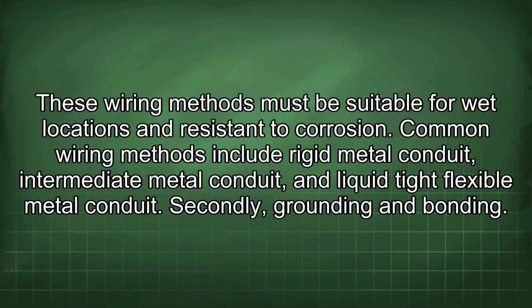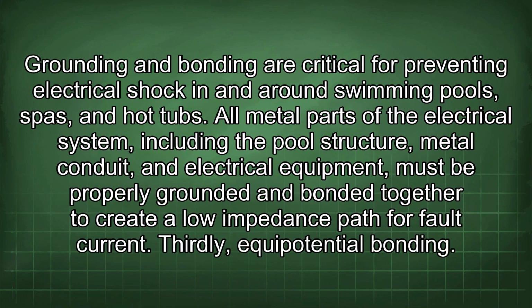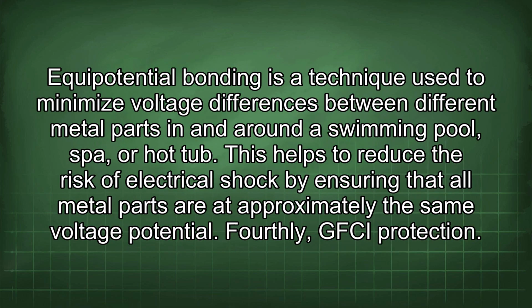Secondly, grounding and bonding. Grounding and bonding are critical for preventing electrical shock in and around swimming pools, spas, and hot tubs. All metal parts of the electrical system, including the pool structure, metal conduit, and electrical equipment, must be properly grounded and bonded together to create a low impedance path for fault current. Thirdly, equipotential bonding. Equipotential bonding is a technique used to minimize voltage differences between different metal parts in and around a swimming pool, spa, or hot tub. This helps to reduce the risk of electrical shock by ensuring that all metal parts are at approximately the same voltage potential.